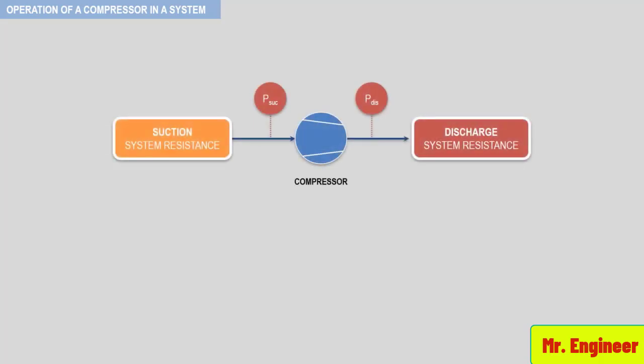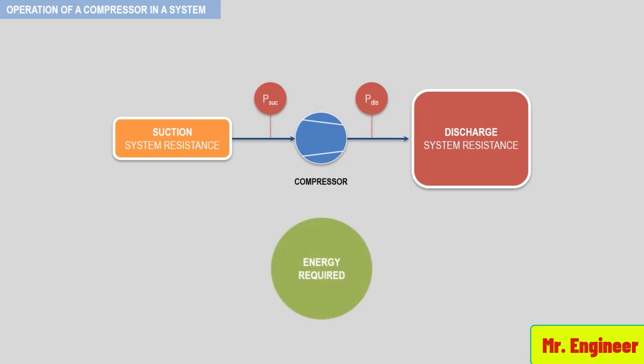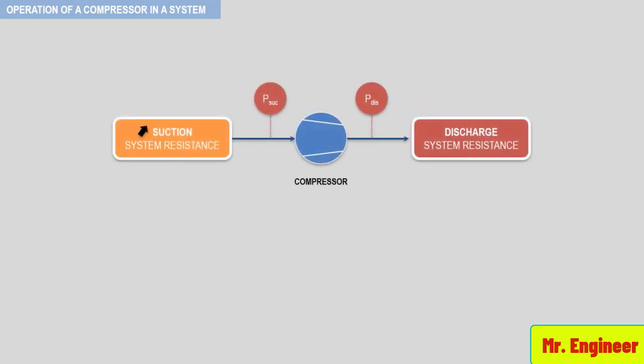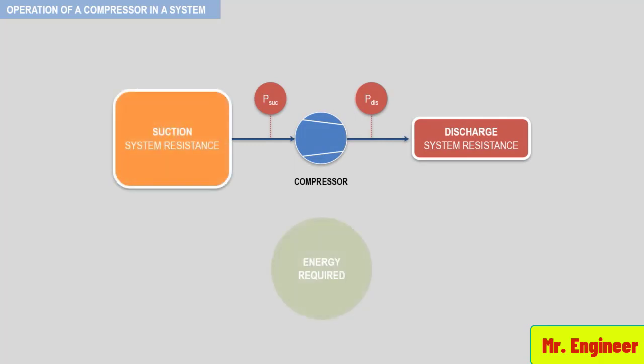Increasing discharge system resistance with a constant suction resistance will result in higher compressor energy required. Also, increasing suction system resistance with a constant discharge system resistance will result in increasing compressor energy required. Many times, the concept of increasing suction system resistance, or suction throttling, is misunderstood. This will be discussed in detail in this section.